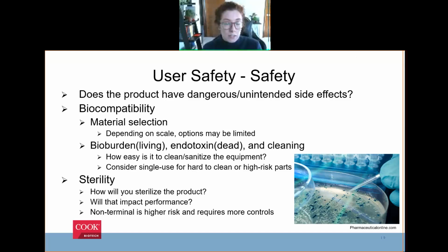So to give you an idea, I recently worked on a product where we were partnered with one of our external companies, and they had been terminally sterilizing this product. And they found that it really negatively impacted the performance, because they were doing an autoclave and it was degrading the material. And so we had to work through with them to figure out, okay, we can't really do that. Maybe you use some other sterilization process in the lab, but now that we're doing this larger scale, we need to do a different sterilization method in order to not negatively impact this product. When I say terminal sterilization, I basically mean the sterilization is the last thing that happens before it gets packaged and then sent out to the customer.